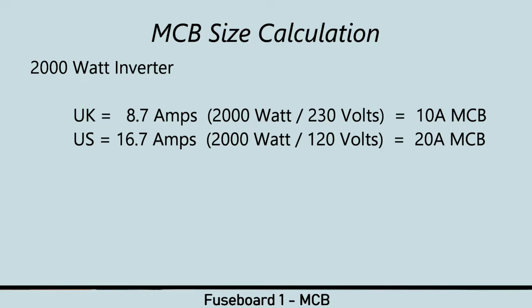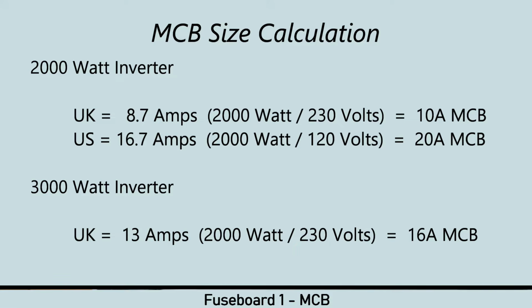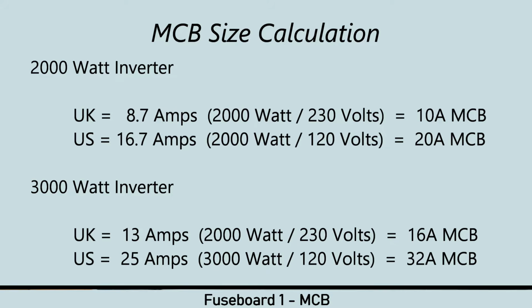Now, America, I'll just cover America. So if you're running 120 volts, that's 16.7 amps. So obviously you're going to need a bigger circuit breaker than what we've got. If you've got the 3000 watt model at 230 volts, you're looking at 13 amps. And if you've got the 3000 watt model in America and you're running 120 volts, then that's 25 amps. So obviously you need to rate your circuit breaker respective of the inverter charger that you're using.